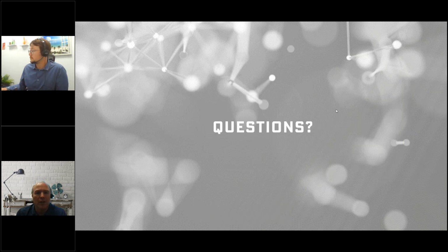All right, here's a question coming in from Bill Flores. What works the best to power a water pump? A low voltage, high current system, or a high voltage and low current system? I'll just read the answer that one of your engineers submitted, and then you can embellish if you'd like. So the answer here is generally using a higher voltage will reduce the cost of the system, since the lower current will allow you to decrease controller size, wire size, and current protection.